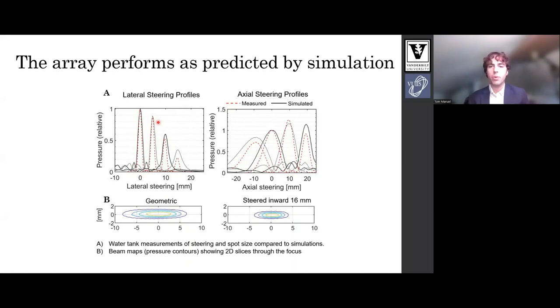We measured that the array performs as predicted by simulations. The top row shows steering results in water comparing measurements and simulations — simulations in black, measurements in red. This is lateral steering on the left and axial steering on the right. We have good steering out beyond ten millimeters with less than 50 percent pressure reduction. The plots on the bottom also show that as we steer inward the focus tightens compared to our geometric focus, which is what we hoped to see.